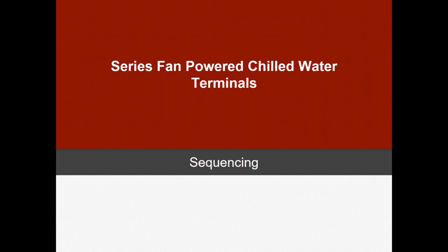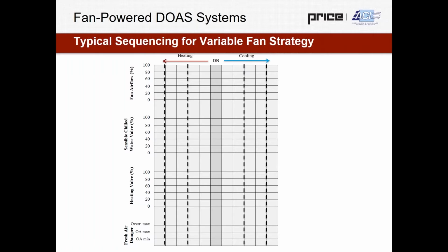So another point of discussion here, just a little bit of quick education. If we look at sequencing of this equipment, I think this is a little understood, or it's at least some good background if this is a newer piece of equipment for you. When we look at the cooling side of sequencing, beyond deadband, the first thing that generally happens is the opening of a sensible chilled water valve. So that's generally the first stage of cooling, whereas the second stage of cooling would be the engaging of a fan and actually the increase in fan airflow.